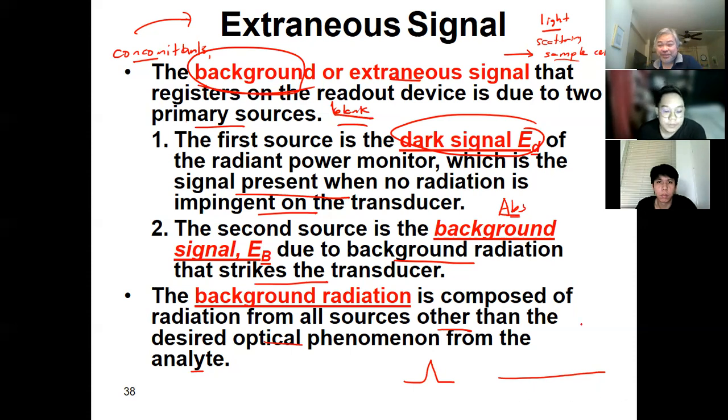I remember last week when we did the UV-Vis, pag sinisiro ko, ayaw mag-zero. Since one wavelength lang siya, sabi ko sa mga estudyante ko, just get the reading of your blank as is, and then you subtract it from the reading of your sample. Yeah, it should be zero, but the instrument won't zero.